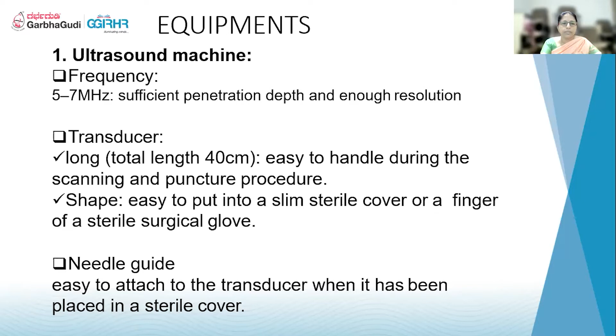Very, very important is attach the needle guide properly to the transducer, very tight when it has been placed in a sterile cover. I have seen once when I had not checked the needle guide and it was very loosely done and I had already started the procedure. I was feeling that something was not okay. Took out and checked, the needle guide was not snug, it was loose. My needle and the guide was going somewhere else. So once the OT technician hands over the probe to you, check the needle guide properly and then insert. That's a very, very common thing to happen.